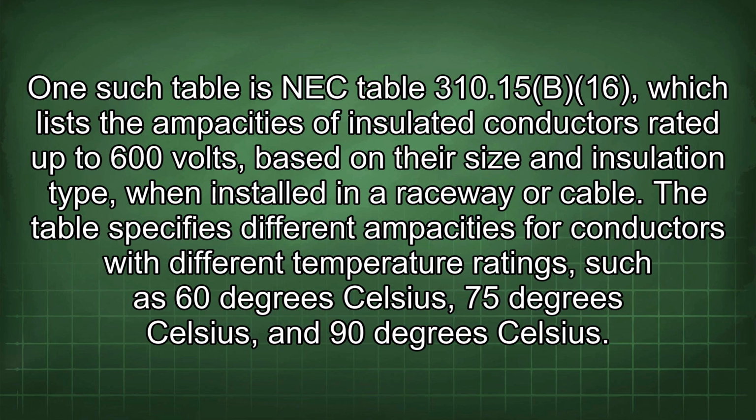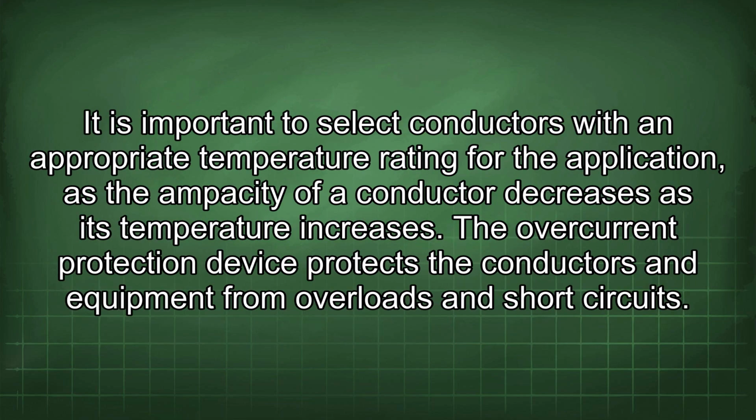The table specifies different ampacities for conductors with different temperature ratings, such as 60 degrees Celsius, 75 degrees Celsius, and 90 degrees Celsius. It is important to select conductors with an appropriate temperature rating for the application, as the ampacity of a conductor decreases as its temperature increases.